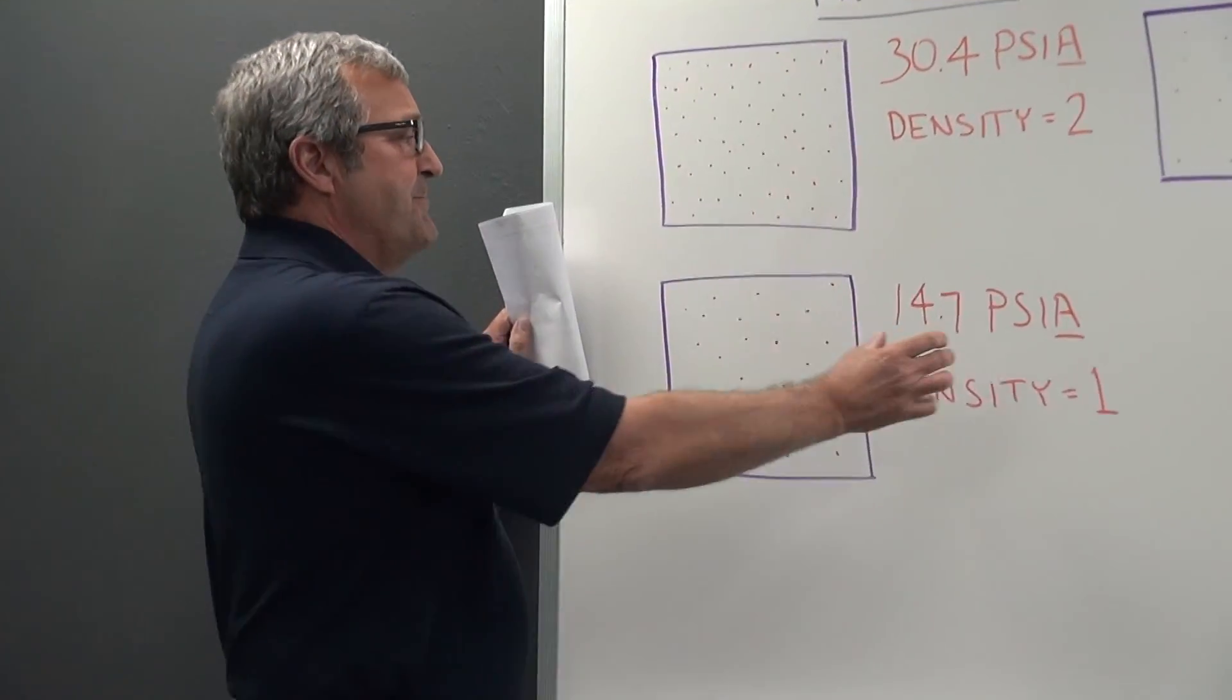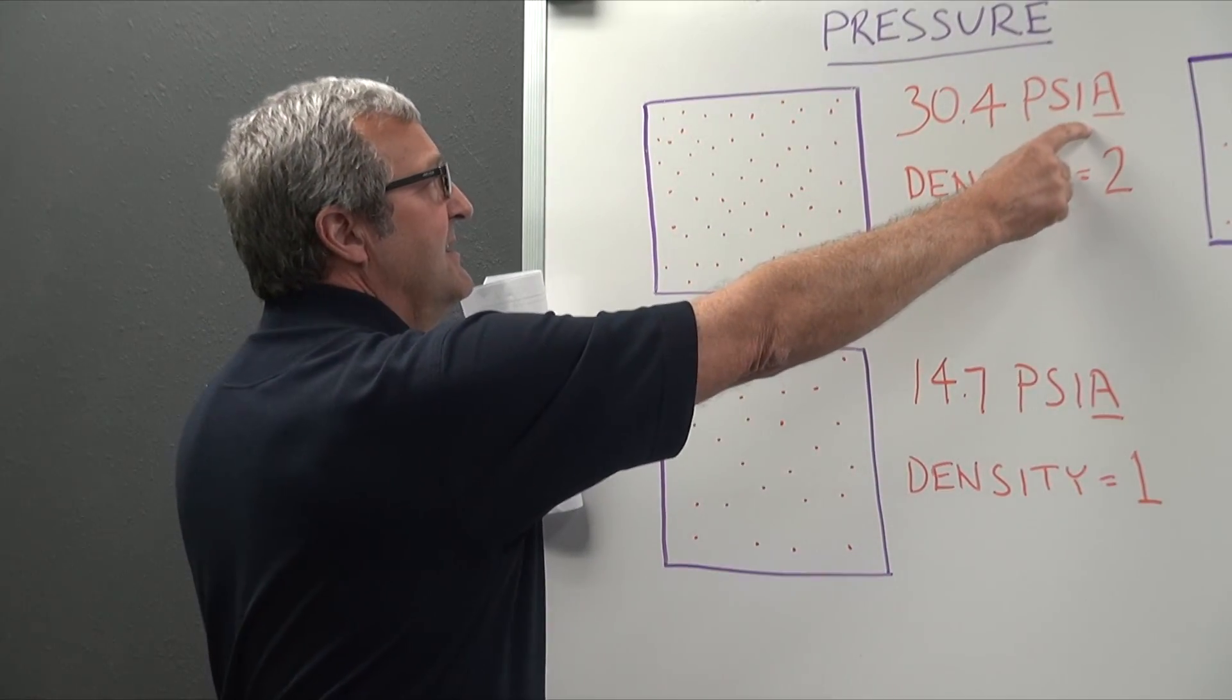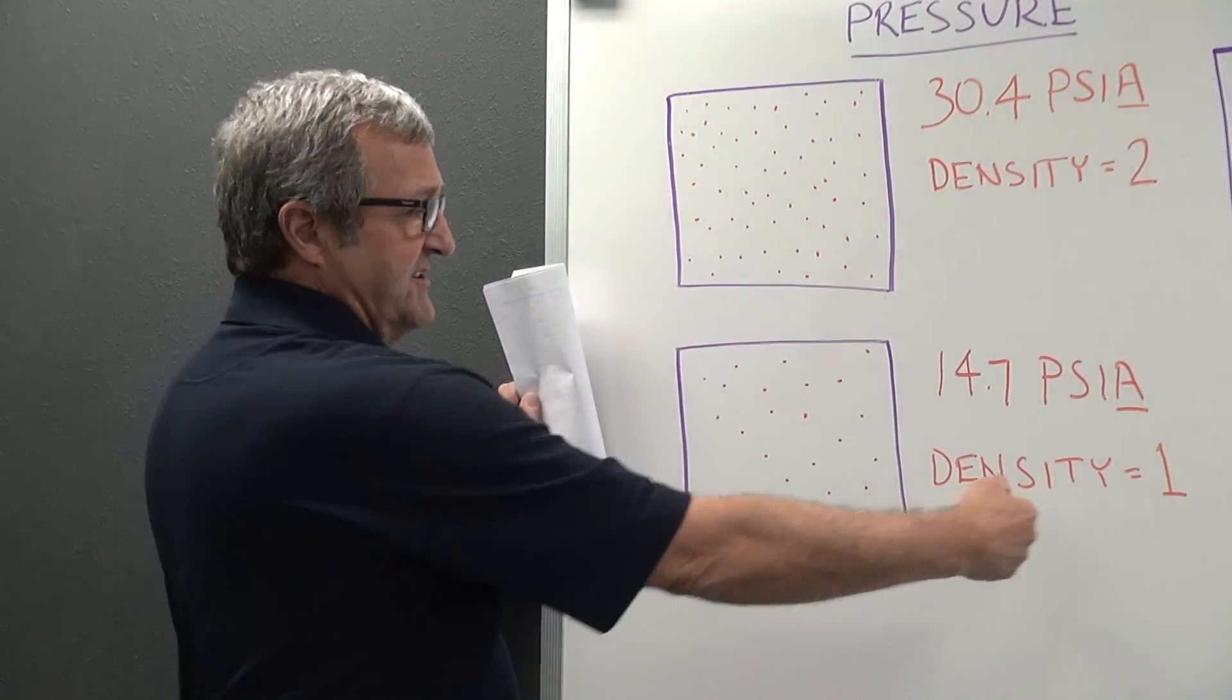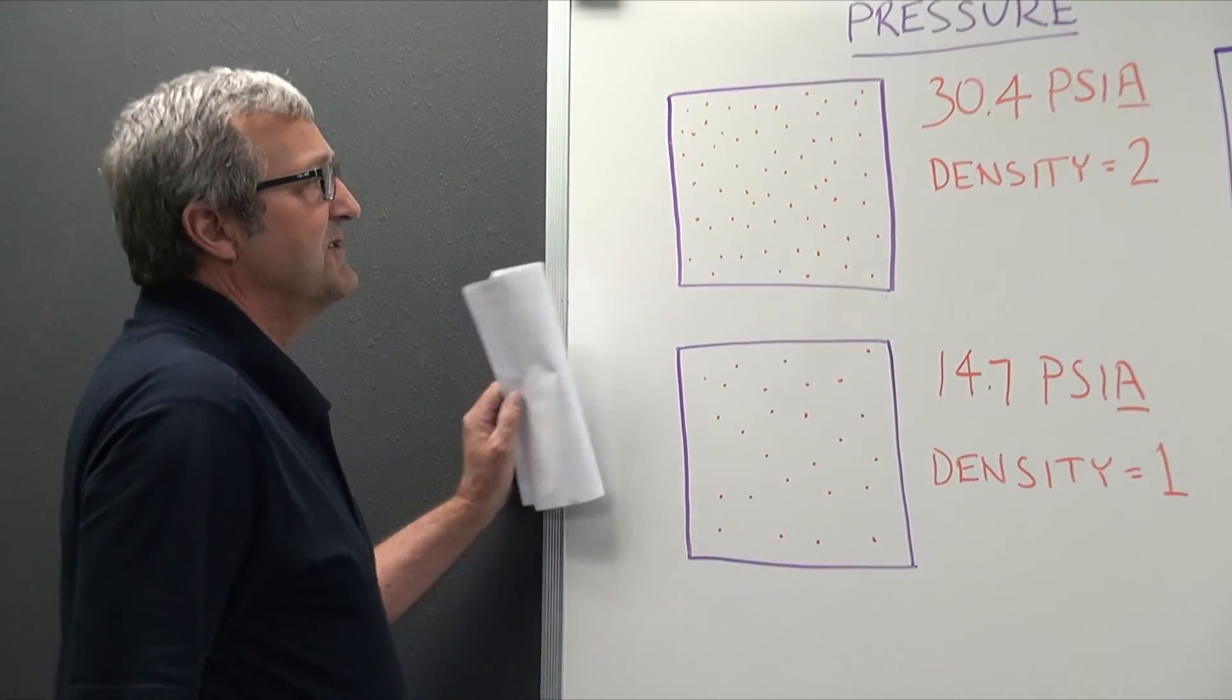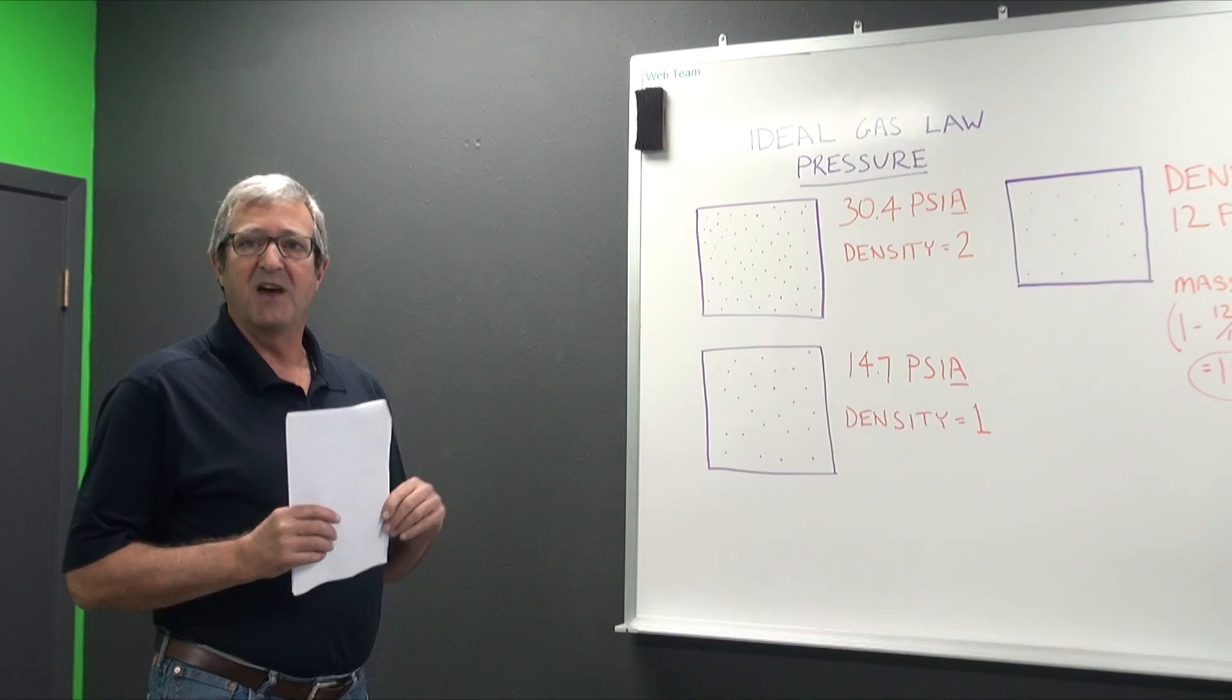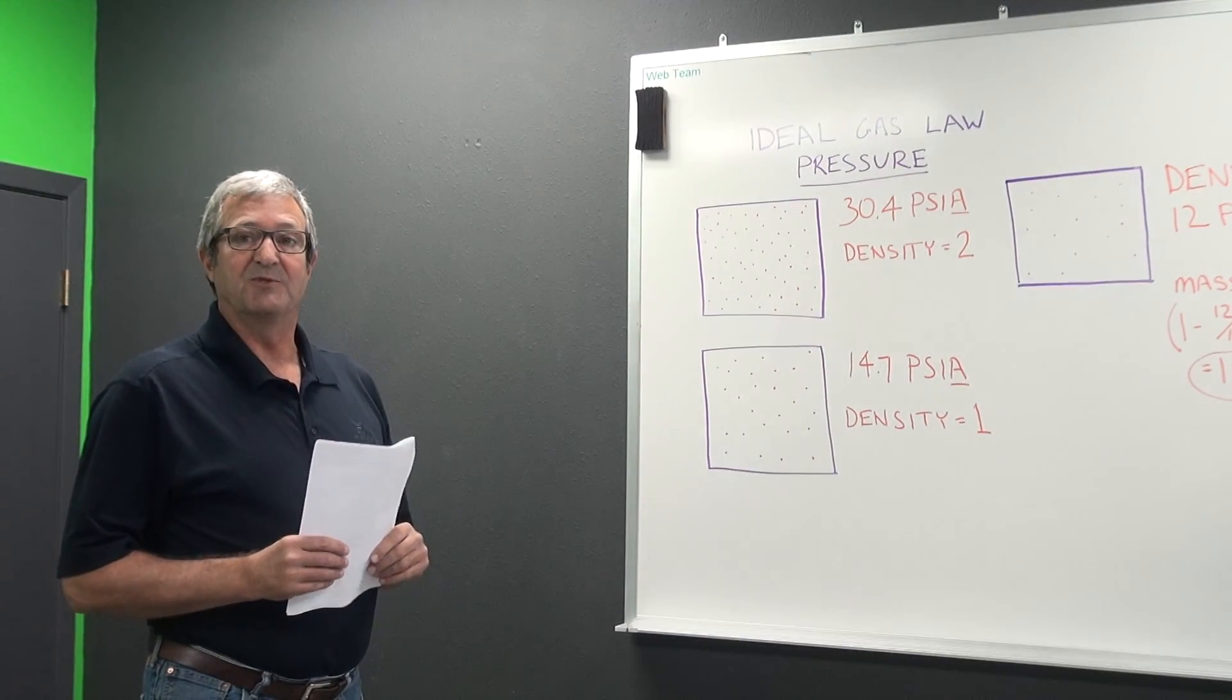Now if you double the pressure from 14.7 PSI to 30.4 PSIA, we've effectively doubled the number of molecules that reside in that same space. Hence the density has increased from one to two. So that's an easy thing to remember I hope and to keep in mind as far as mass flow is concerned compared to volumetric flow, that these flows are very sensitive to pressure is what we're trying to show here.